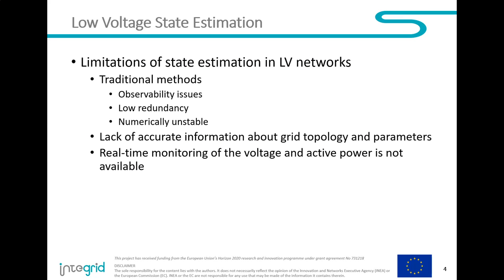Another problem — a limitation on the low voltage grid — is state estimation. With traditional approaches, you have observability issues. Smart meters collect all data but only provide it once per day, usually at end of day — a critical limitation if you want to know the operating conditions in real time. You have low redundancy: if one smart meter fails, you lose that measurement. There is also numerical instability because you often lack the network topology, or the topology data has many gross errors from field mapping.